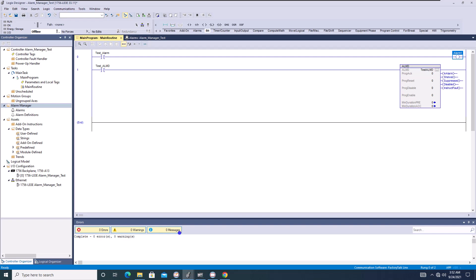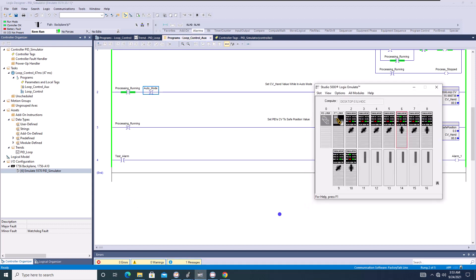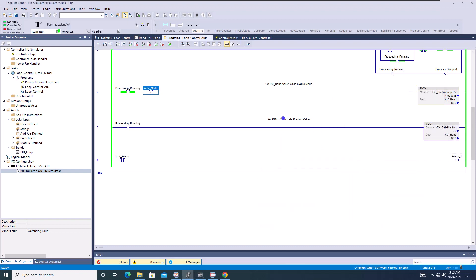But just keep in mind, this is, and also too, you cannot use it in the emulated form. So if you are trying to use it with an emulator, and you currently see I'm in slot six of this emulator. So Logix Simulator, Studio 5000 Logix Simulator, doesn't matter which version you have, you are not allowed to use the alarm manager.